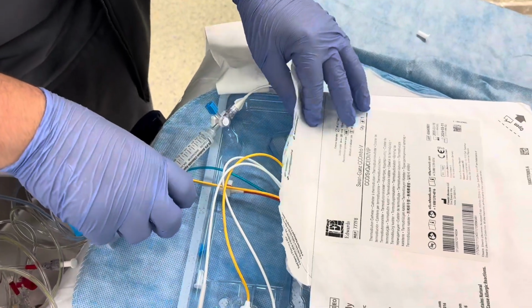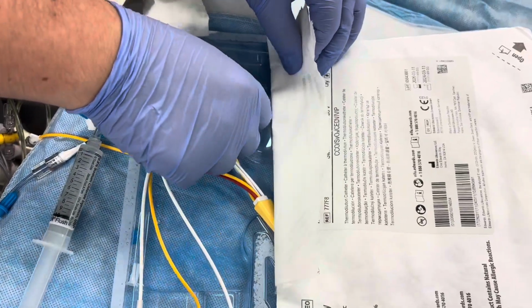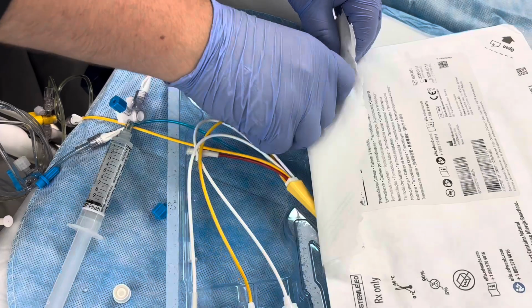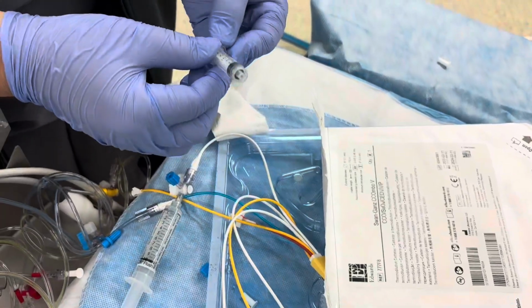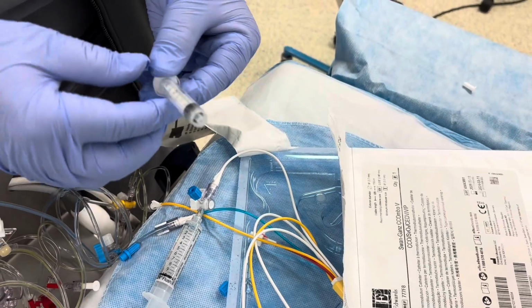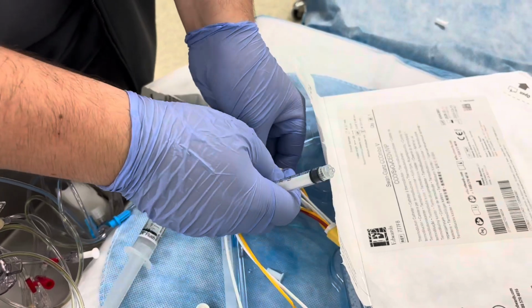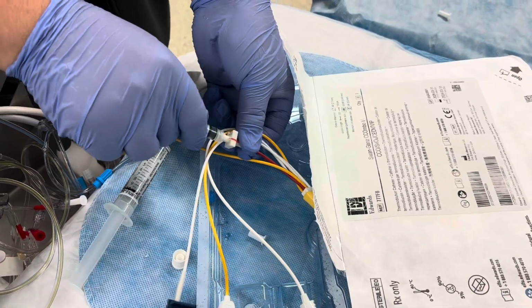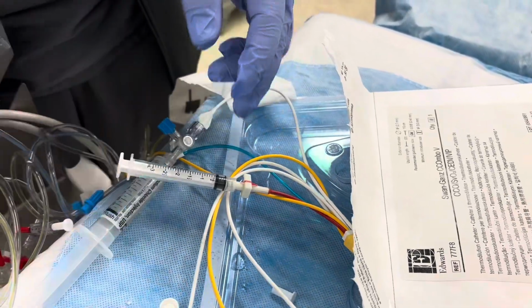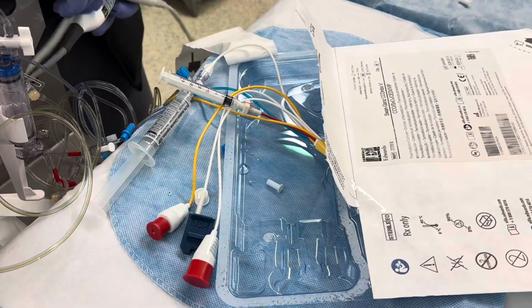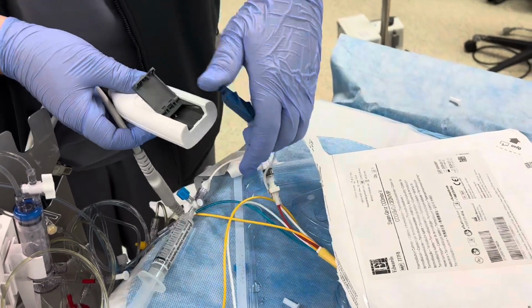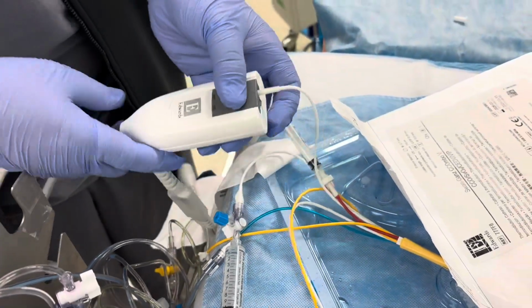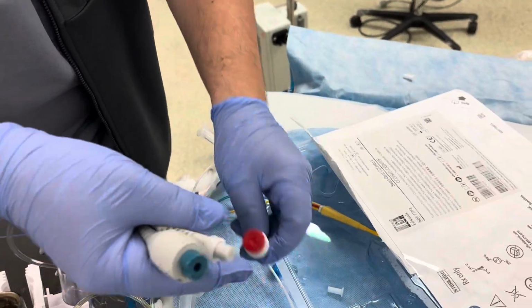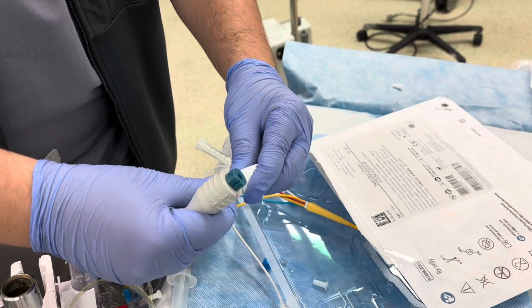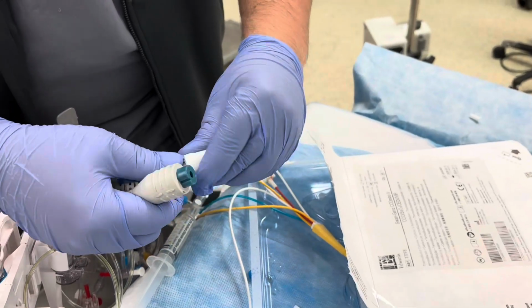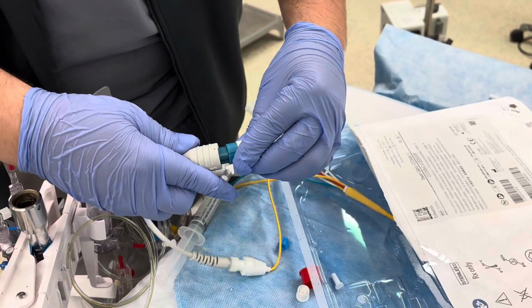Just like that. And then you'll see the kit comes with a syringe inside. We'll take that syringe. This is a special syringe that only allows a certain amount of air to go into the balloon. So only use a syringe that comes in the kit. Don't use another 3cc syringe from outside. Just only use the one in the kit. And we'll connect it to this red port right here. Okay. Then these three cords. We have our cord set up. Just connect these to the Swan, to the Edwards machine. Okay.